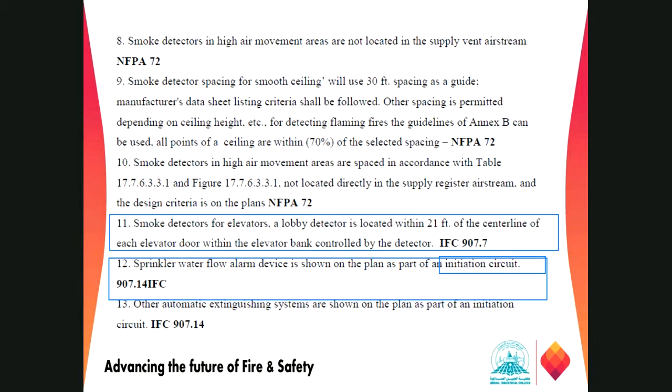A person came, they installed their sprinkler system, all piping and all, and there is a fire alarm system. We need coordination between two teams because we have to connect the water flow alarm switches all the way to the fire alarm control panel to supervise those. So we need coordination from these two parties, and sometimes they just forget that, and on the last day of commissioning they point out these points.